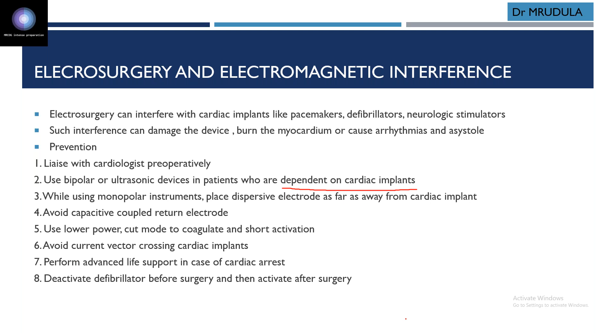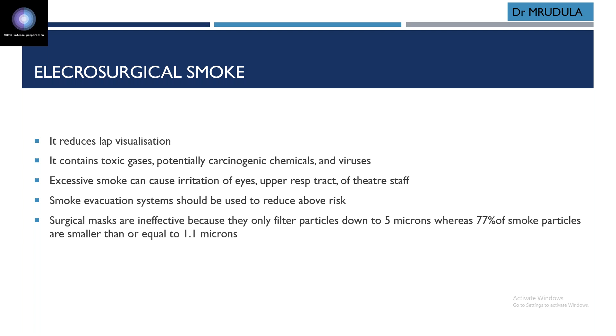Now, electrosurgical smoke is again a cause of concern. It reduces laparoscopic visualization. It contains toxic gases, potentially carcinogenic chemicals, and viruses. Excessive smoke can cause irritation of the eyes and upper respiratory tract, including to the theater staff. So a smoke evacuation system should be used to reduce the risk. Surgical masks are ineffective for electrosurgical smoke because they only filter particles down to 5 micron, while 77% of smoke particles are smaller than or equal to 1.1 micron.